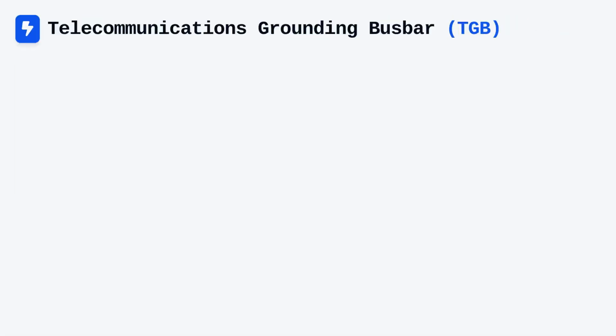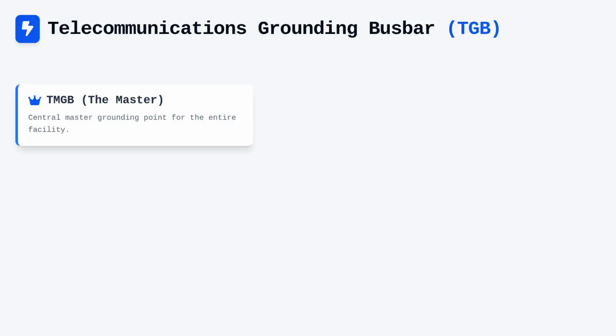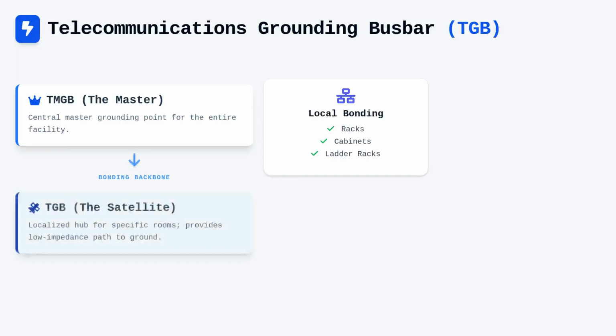Moving away from the entrance, we encounter the Telecommunications Grounding Busbar, or TGB, which acts as the localized grounding hub inside each individual telecommunications room. While the TMGB is the master, TGBs are the satellites that facilitate local bonding for racks, cabinets, and ladder racks within their respective spaces. The TGB is connected directly back to the TMGB via the telecommunications bonding backbone, a conductor which I will elaborate on shortly. Effectively, the TGB provides a low-impedance path to ground for all information technology equipment housed within that room.